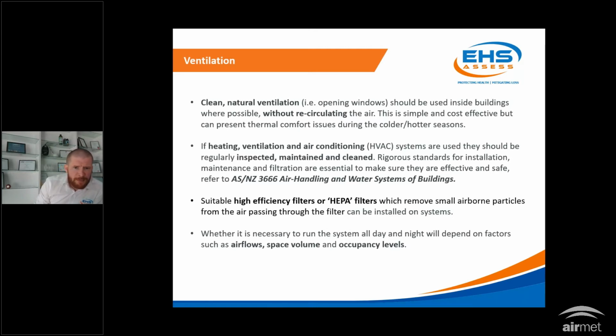Overall, whether your system needs to run all the time, whether you run it at nighttime, whether you start it in advance of classes opening, or run it after people have been in the room, it's all unique to your building. The factors that affect that overall are airflows, the volume of space you're in, and occupancy levels. Occupancy levels are really, really important, and we'll talk about those in the next couple of slides, where we introduce the concept of carbon dioxide and monitoring carbon dioxide as a measurement for overall ventilation.